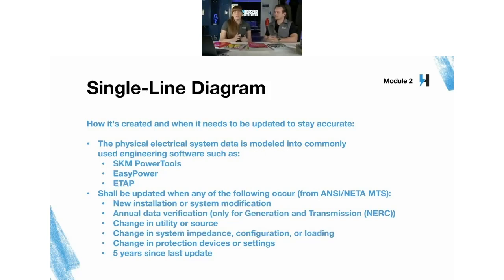Now, what about how often it needs to be updated so it stays useful? Well, the 70E talks about the arc flash portion of it, and if there's any change to the electrical system, you must update your study for arc flash. But that'll end up changing your one-line anyway. One of the things about these one-line diagrams is that they're really only helpful and useful if they're correct.